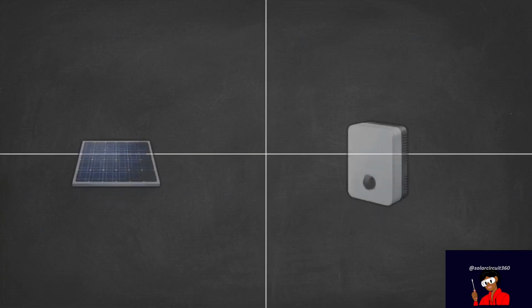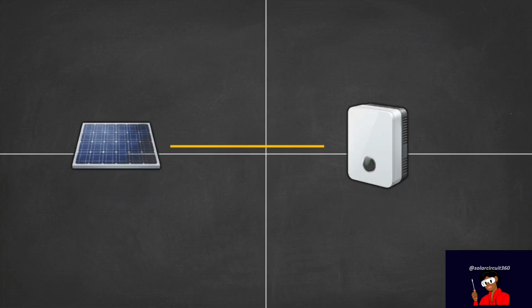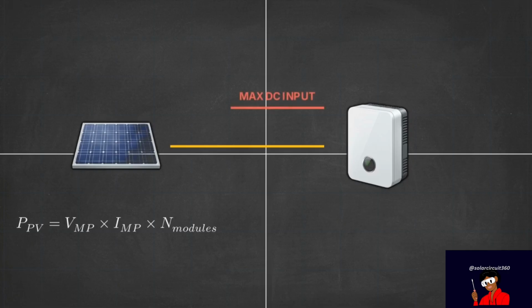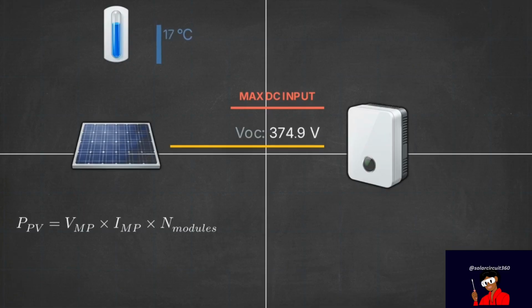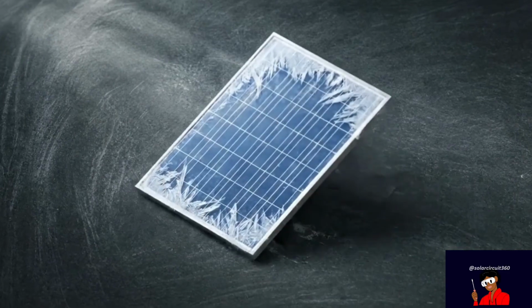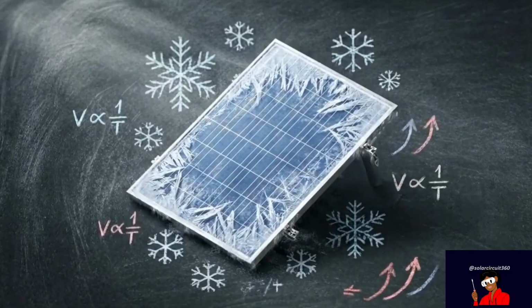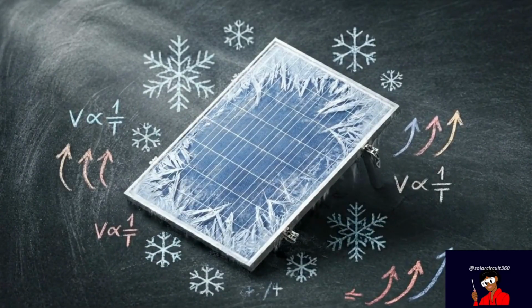The model begins with the primary energy source, the photovoltaic array, connecting to the inverter's direct current inputs. To align the array with the inverter's capacity, we multiply the maximum power voltage by the maximum power current, then by the total number of modules. We must also account for the open circuit voltage, or VOC, the maximum voltage produced when no load is connected. Cold weather is a critical variable. As temperatures fall, VOC dynamically scales upward, breaching the inverter's maximum DC input threshold. Solar panels become more efficient at colder temperatures. This inverse voltage scaling inflates the array voltage far beyond standard test conditions.